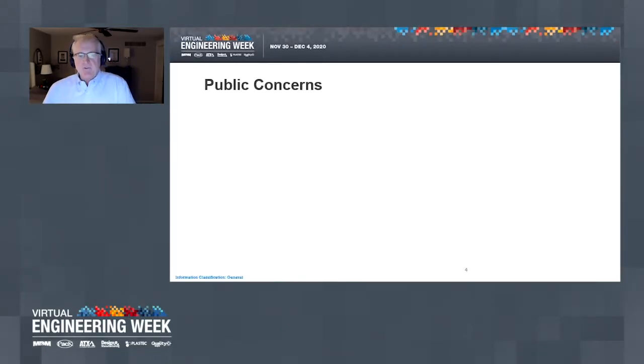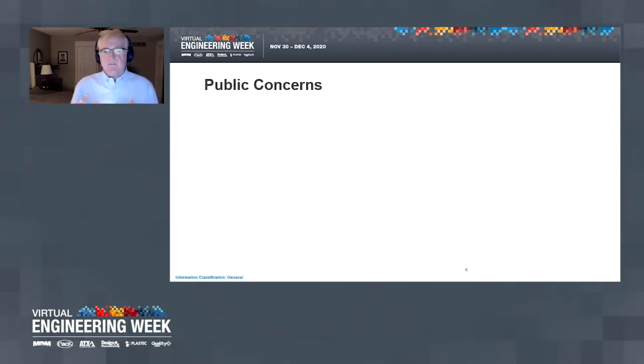So what happened to make EO as a sterilization agent for medical devices a public concern? Well, the flag was tripped back in February of 2019 when the Illinois State EPA issued a seal order on the Sterigenics Willowbrook facility. This order was triggered by the residents living nearby the facility and protesting the EO emissions that facility was producing in their neighborhoods. Now, there is a lot of history on this issue, and I won't even attempt to delve into any of the legal or business aspects of it.